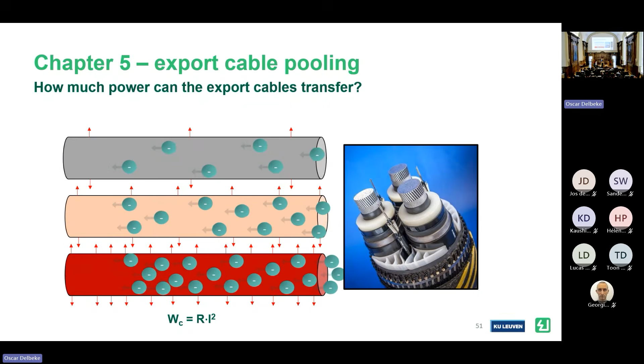I have these specifications, and I could use them, with a thermal model, to simulate the thermal behavior of this cable. What I see with the specifications from Elia and this thermal model from literature is that these cables have a very, very big thermal inertia. The time constant is more than 4 days, and this is the time it takes to reach about 63% of the maximum temperature with nominal power.